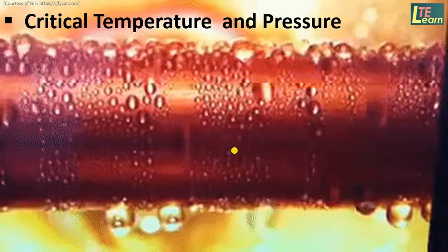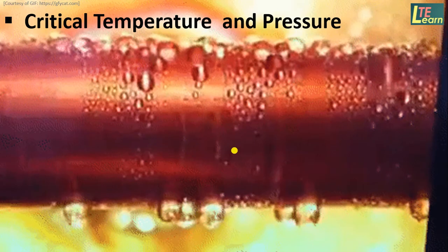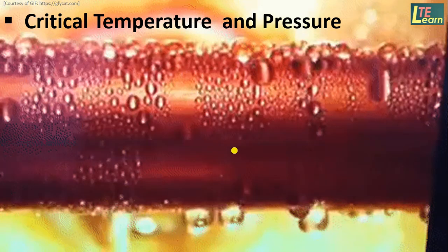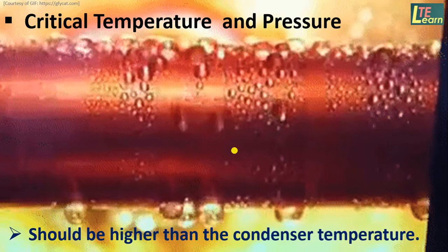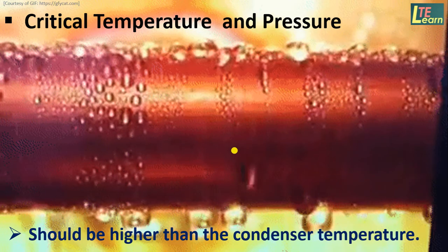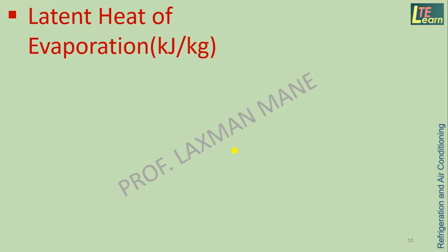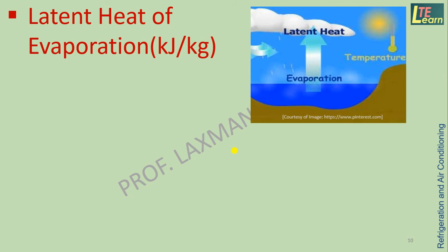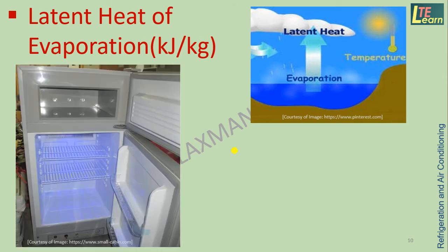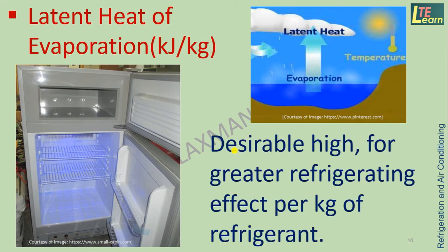Critical temperature is the temperature above which it is not possible to condense or liquefy the refrigerant. Hence, the critical temperature of the refrigerant should be higher than the condenser temperature. Latent heat of evaporation of the refrigerant is the amount of heat in kilojoules absorbed by 1 kg of refrigerant from the space to be cooled, and it should be high for a greater refrigerating effect per kg.